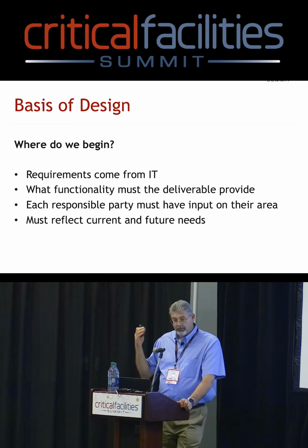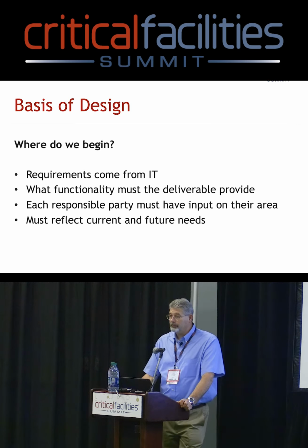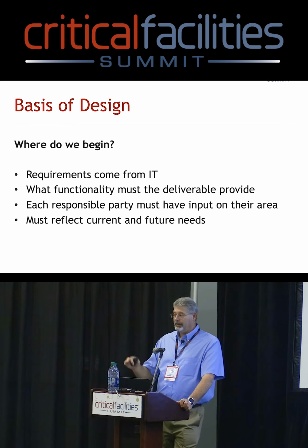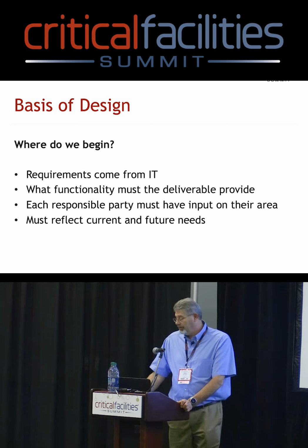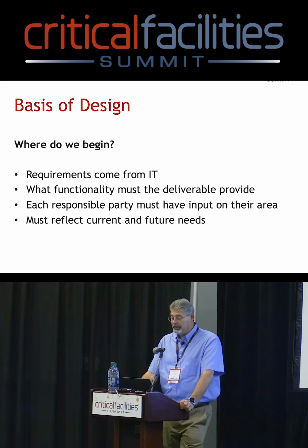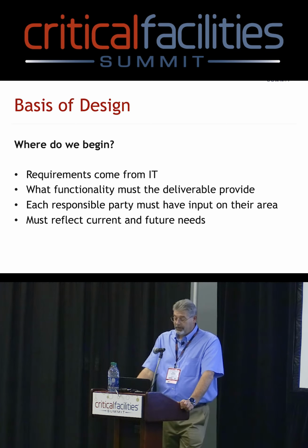Design should entail if you're going to feed from above or below. How many of us have a problem with cabling, power feeds, and things like that under the raised floor? The design phase is when you get ahead of that. You can go back and retrofit. It is completely possible to clean out, but that's generally after the fact and you already have a problem. So everybody needs to agree in the design phase.